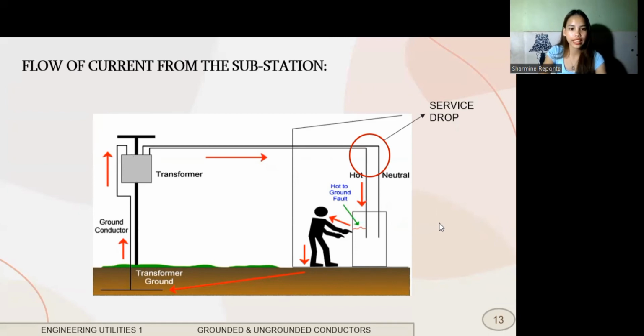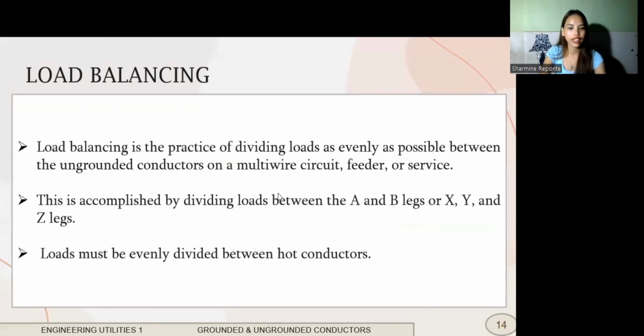So I hope you understand it. Next we have another topic for this chapter, which is load balancing. Load balancing is a practice used when we have two or more ungrounded conductors. Loads are divided between A and B when we have two ungrounded, and X, Y, and Z legs when we have three wires of ungrounded. It is important na sa isa ka circuit dapat balance ang loads ang ginadala nila, or else it will cause a fault or problem in the wiring system. For example, we have 18 ampere. It will be divided in two. So each wire will carry 9 ampere na lang. So that's what we call load balancing.